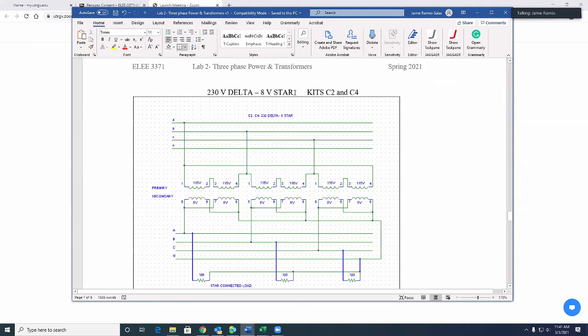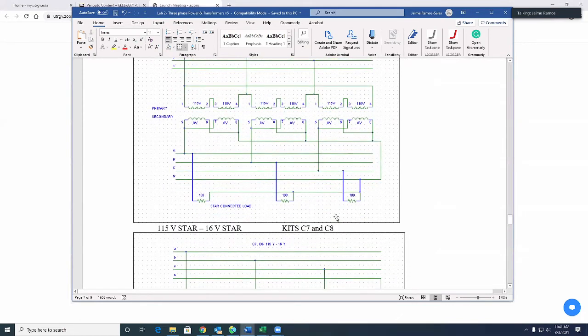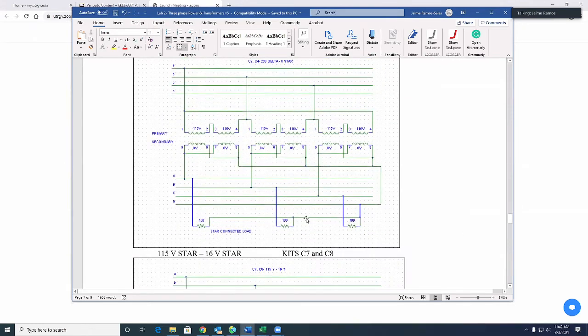And since we specify a star connection, then in the secondary, the neutral right here is connected to A, B, C. Yeah, it's right here. Look, all terminals number 8 of the secondary are connected to the neutral right here, and then also we have 100 ohm resistors connected to phases A, B, C and to the neutral. Okay, so this is the connection that we are using.